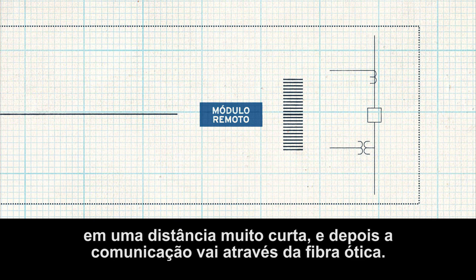Pretty cool. About 15 years ago, the IEC committee started working on how to standardize this so that you can have multiple vendors work on it. The IEC committee came up with what's called the IEC 61850-9-2 sampled values. What they ended up with is a relay compatible with that protocol, and then the remote module in the yard, which they called a merging unit.